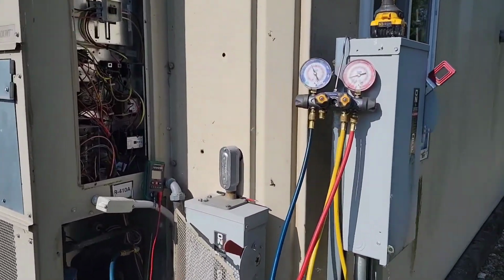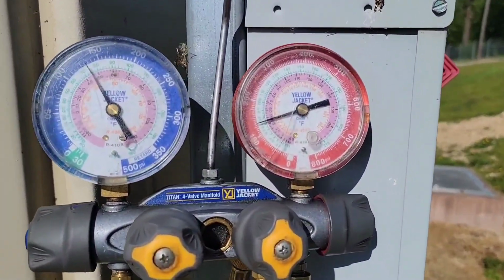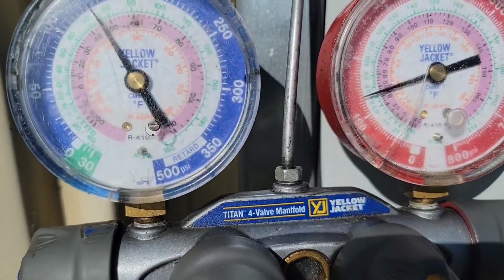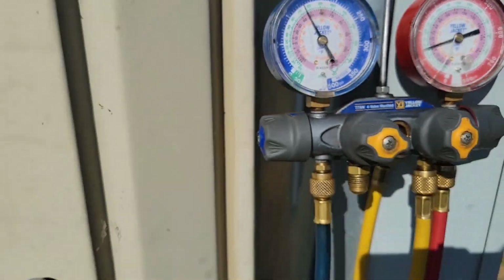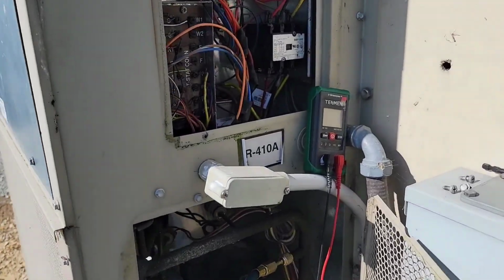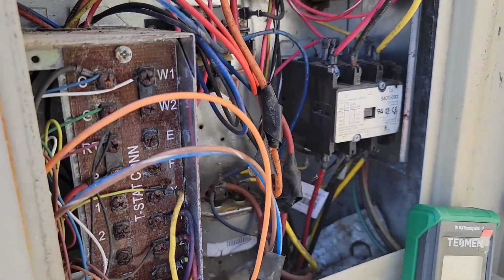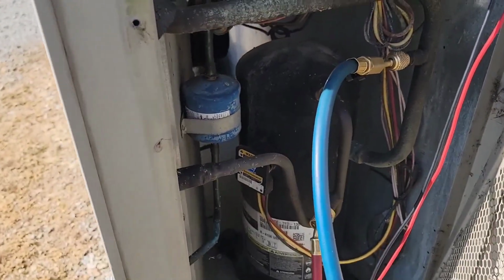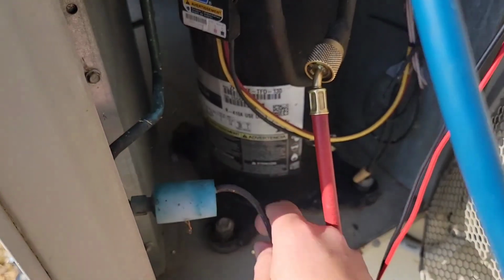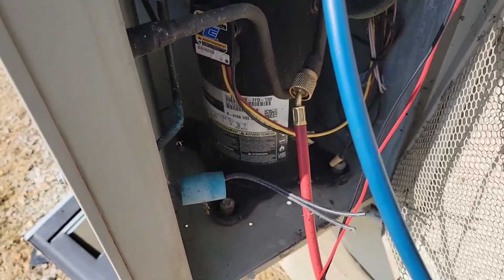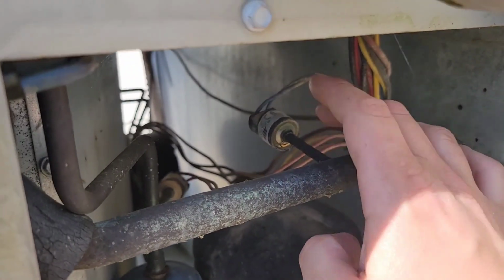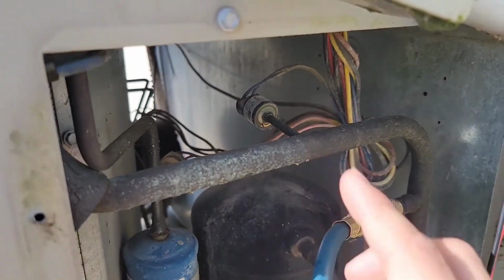Okay, so this is 460 volt 3-phase. We got our gauges hooked up. We got pressure. Okay. So let's figure out why the compressor is not running. So looks like we got a head pressure control right here that's been cut. We got a low pressure control right here that's still wired up.